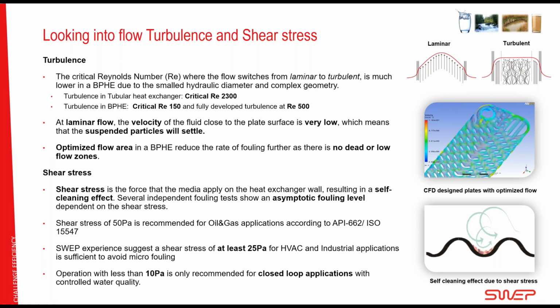What I also like to point out is the optimized flow area that I mentioned before, that since SWEP has been able to work with the whole plate, since it's a brazed plate and not a gasketed, we see that we have turbulence in all parts of the heat exchanger, and there is no dead areas or low flow zones.